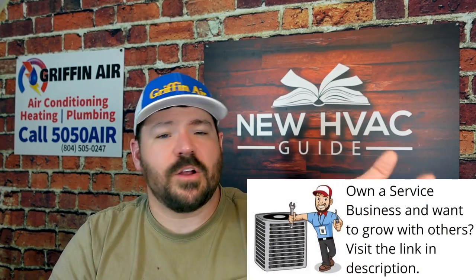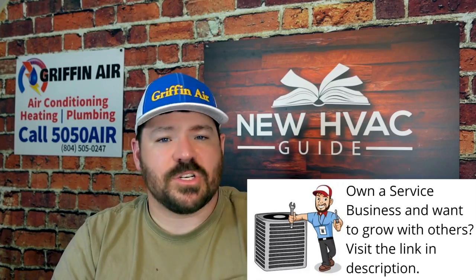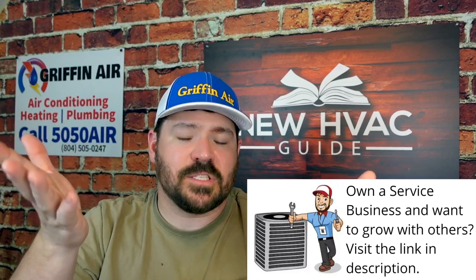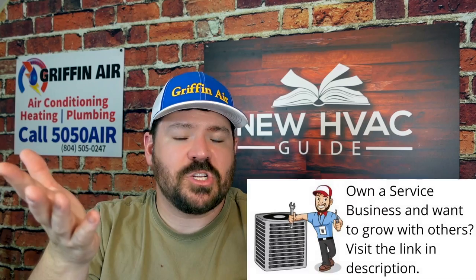I get this sometimes. Folks will say, well, I had a system in here before that ran for 15 or 20 years just fine. Then we got this new system put in, and we're having nothing but issues, and you're telling me the ductwork is the problem? We've had to do that a few times at Griffin Air, going behind another company because the homeowners call us when the other company can't figure it out, and we find the ductwork is undersized.